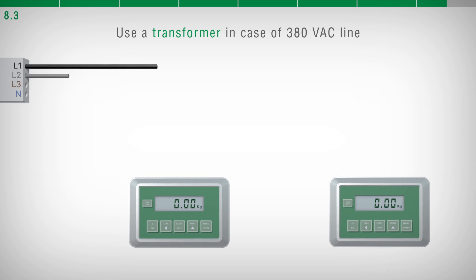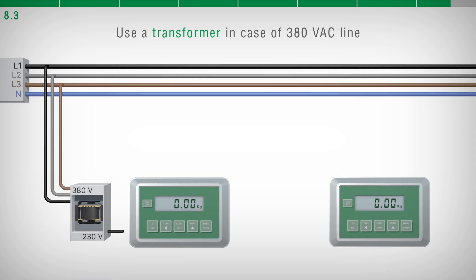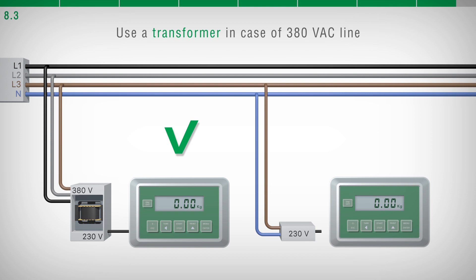In case of power supply 380 VAC, a 380 to 230 VAC transformer must be used. Do not use a 380 VAC phase and the neutral one.